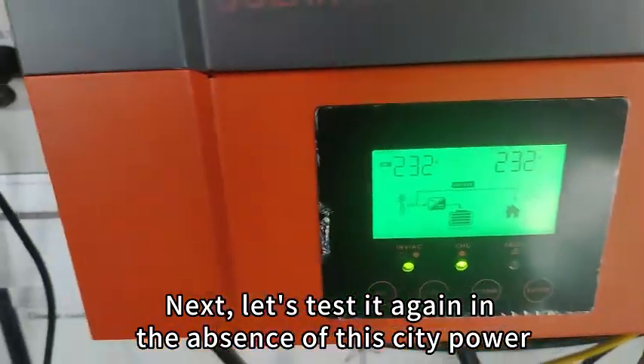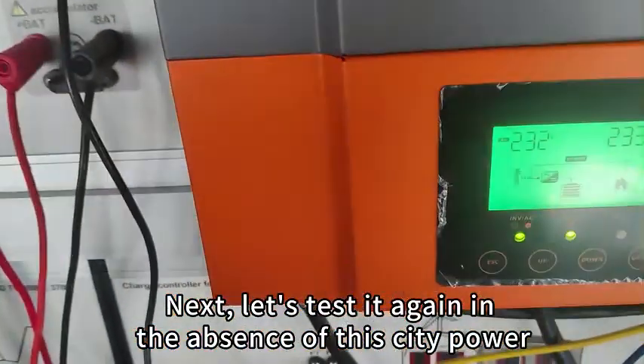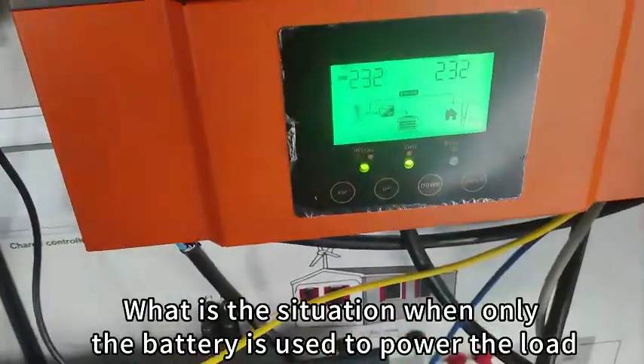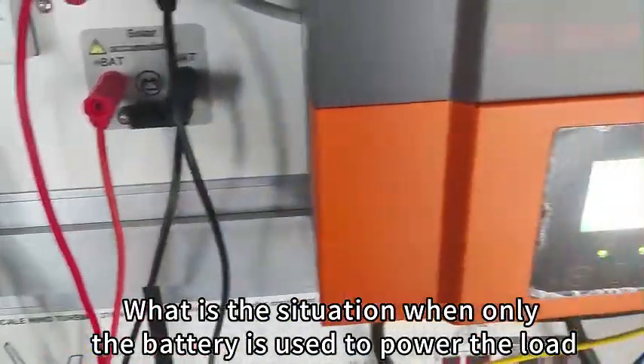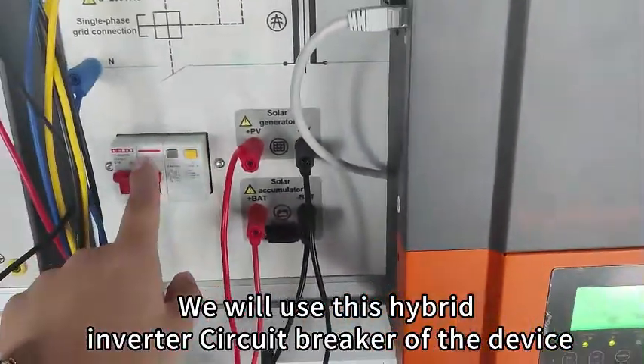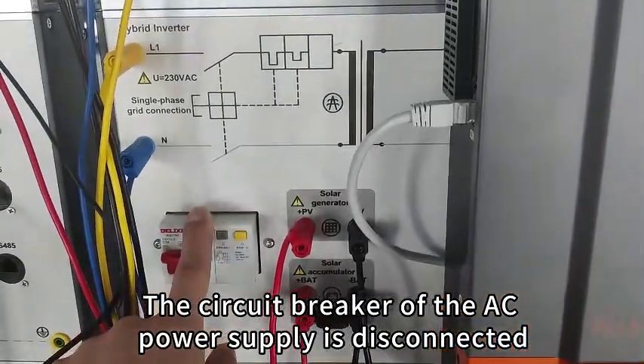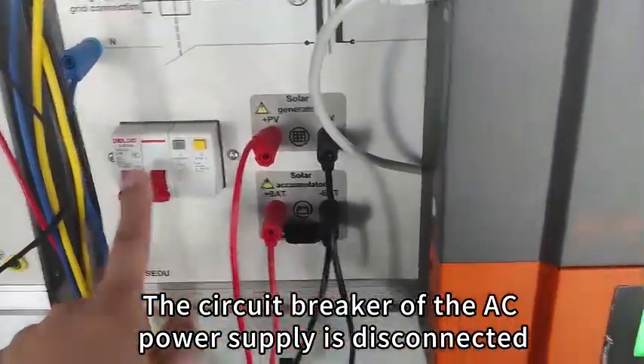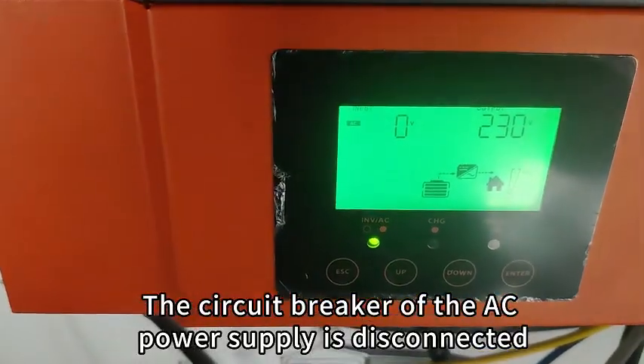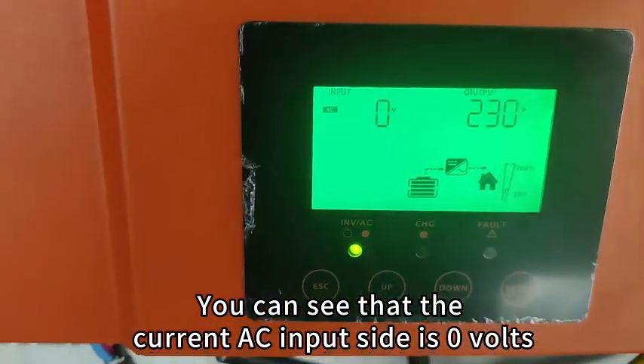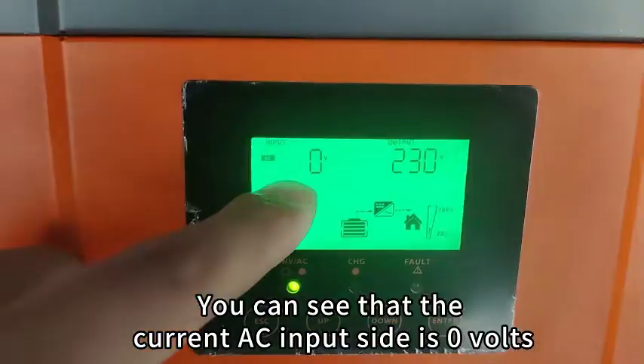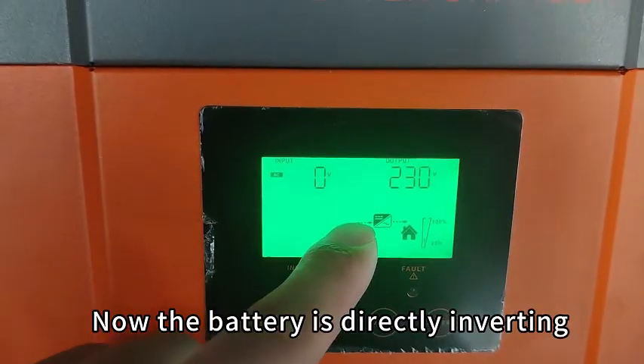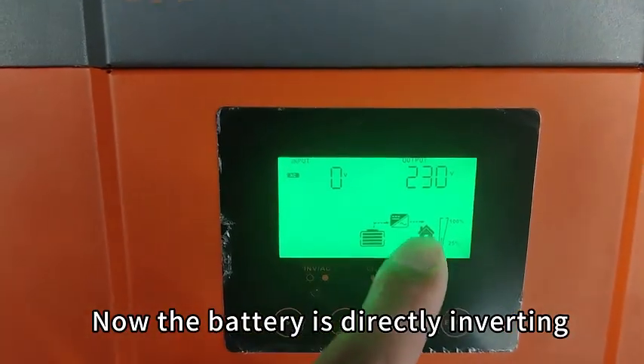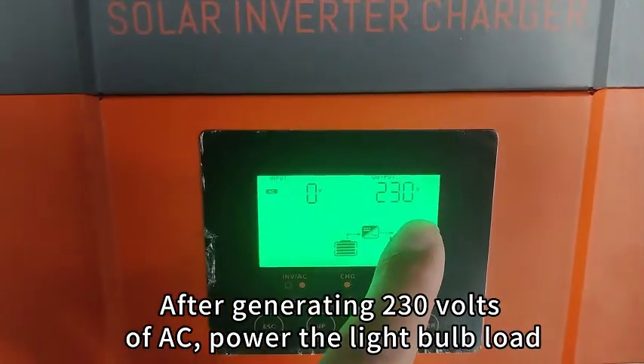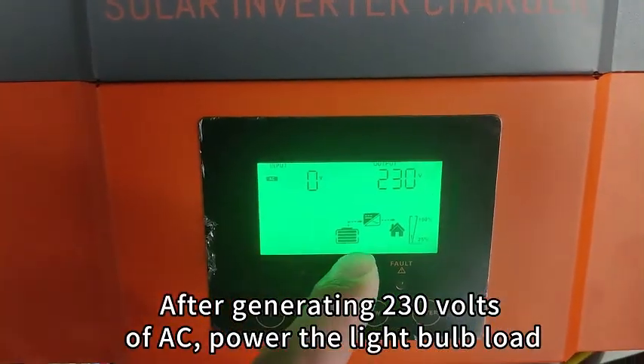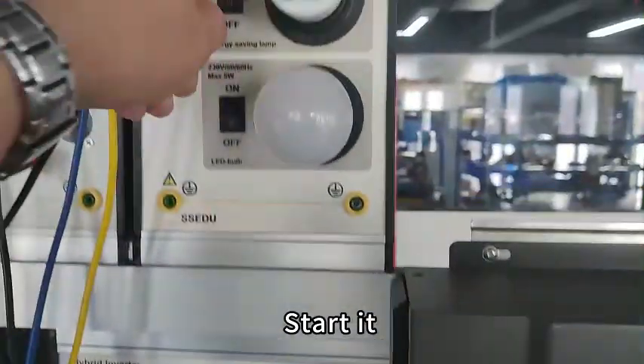Next, let's test it again in the absence of the city power. What is the situation when only the battery is used to power the load? We will use this hybrid inverter circuit breaker of the device. The circuit breaker of the AC power supply is disconnected. You can see that the current input side is 0 volts. Now the battery is directly inverting. After generating 230 volts of AC, power the light bulb load. Started.